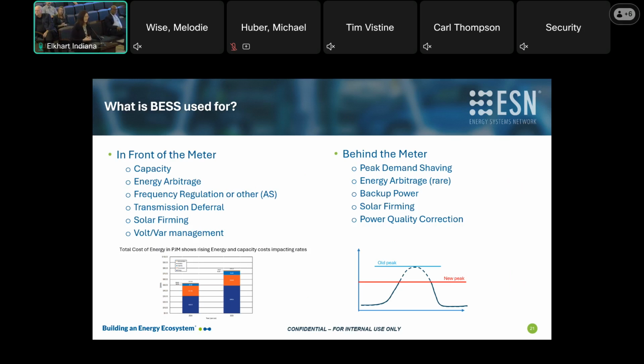Behind-the-meter applications would be if a factory were to buy a battery energy storage system for their own use, for example. The main reason a factory would find that economically beneficial is that, as many of you know, factories pay something called a demand charge, which reflects the peak power they consume during the month. The battery energy storage system can help flatten their curve by discharging to meet that demand, so they don't have to pay as much in that demand charge.